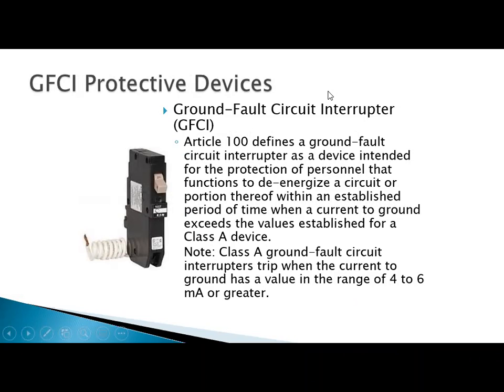And I said breakers protect equipment. That is true until we get to some specialized breakers. This is a GFCI circuit breaker, and we can see that it has a range that it's going to trip at for ground fault current, between 4 to 6 milliamps. The UL standard 943 on circuit breakers was adjusted in 2008, and they do allow this ground fault current now to be only 6 milliamps or more to help us with nuisance tripping a little bit. These are Class A devices. That means that they are going to trip at 6 milliamps or more.